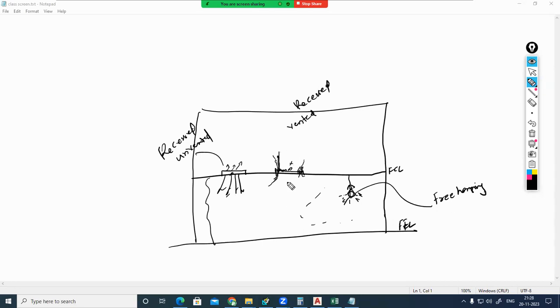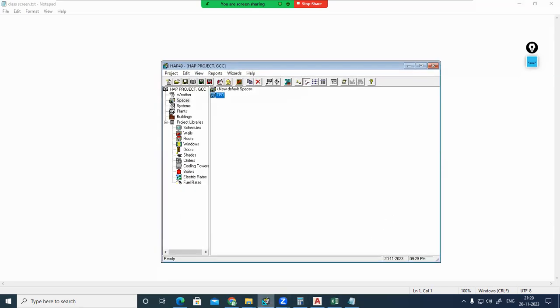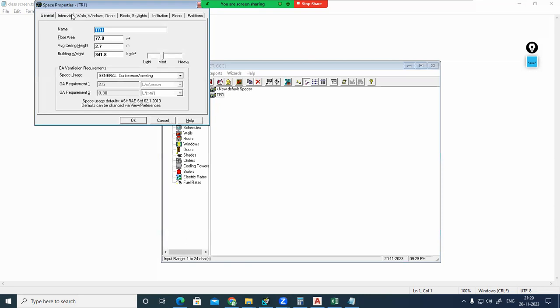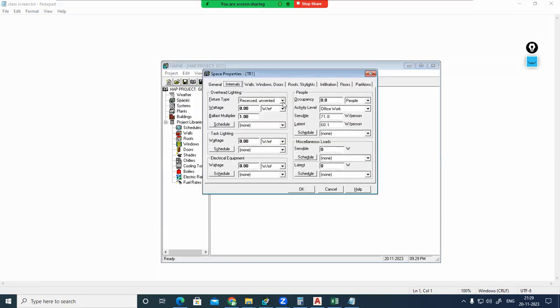Anyhow, recessed vented is not widely used, but if you are using it, you can select it. What type of light fitting it is, the perfect details will be obtained from the light manufacturers only. So for a pre-designed or standard value, normally we will be using recessed unvented type. You can select recessed unvented. If you are using free hanging, you can go for free hanging. So for training room one, internal, you can select recessed unvented, vented, or free hanging. Standard one, recessed unvented, you can select.